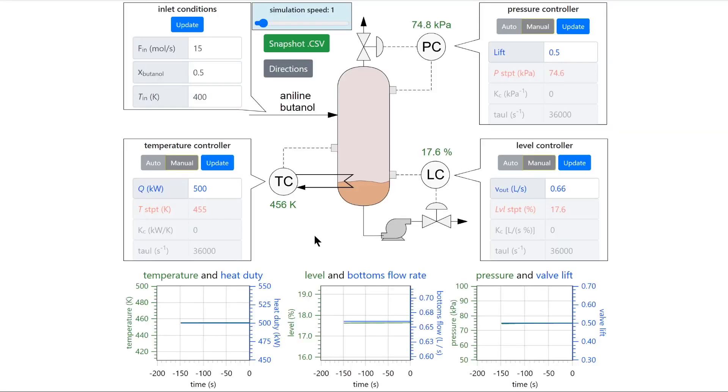To characterize each controller you will need to perform a step change to the manipulated variable. In this video we will do a 10% step change to the heat duty then record and analyze the response of the process variable which is temperature.